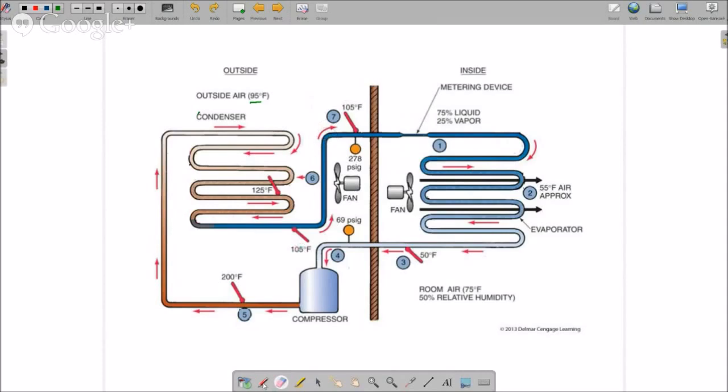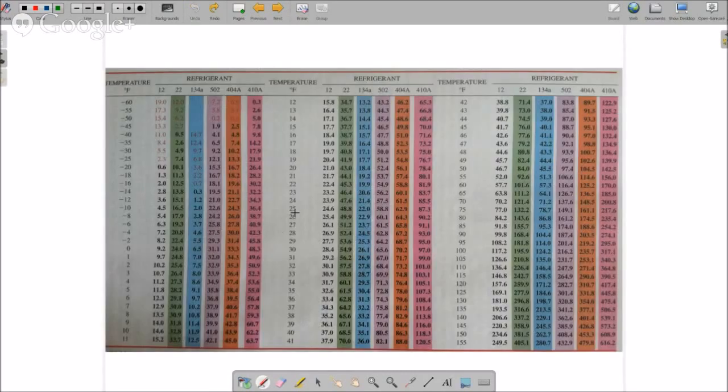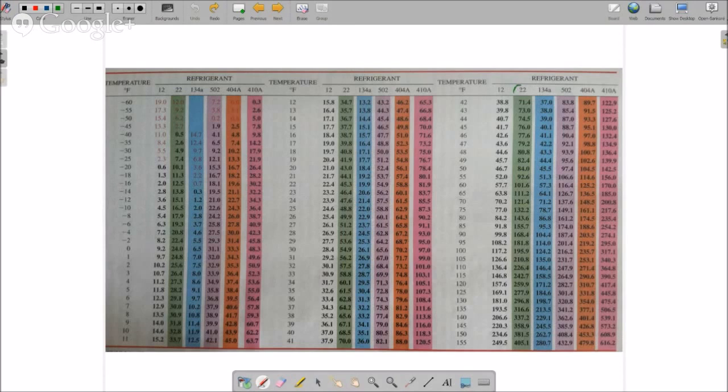We have our gauges on the system and right here you're sitting out at the condenser with your gauges. You're looking at 278 psig on your gauge, so you're going to look at your pressure temperature chart and look over here at R22. This is that column right there, this is from our textbook.